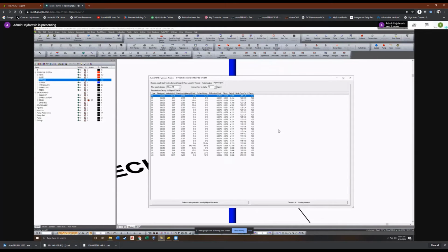Understood. So again, you're utilizing a factory pump curve. The pump manufacturer is going to certify whatever pump at the rating that is specified, but when it's installed, it's going to overperform. There's not a pump manufacturer that produces a pump that doesn't overperform. So again, what's appropriate from an engineering standpoint is entirely up to you to determine. But we certainly can do it.